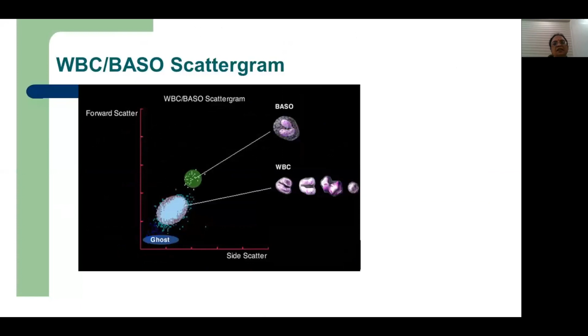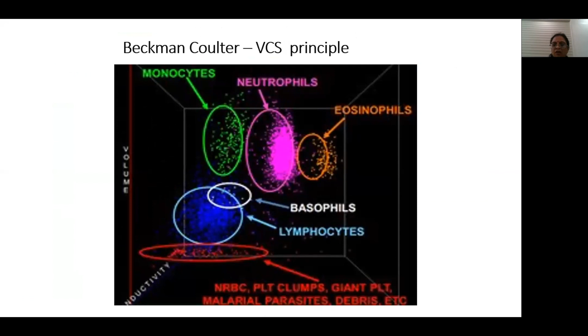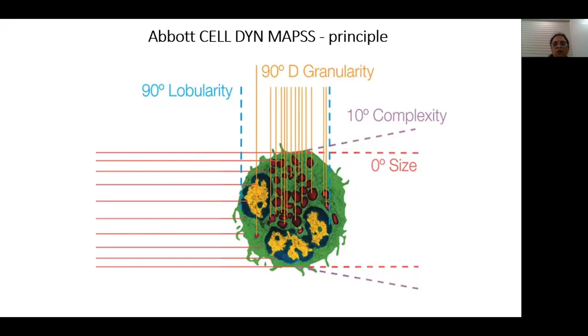And coming to the various hematology analyzers available in the market, Beckman Coulter utilizes the principle of volume, conductivity, and scatter to classify the WBC series. And coming to Abbott, which uses the MAPSS technology, wherein 2 additional light scatters are taken into consideration. The narrow angle light scatter, that is 0 to 10 degree light scatter, is used to note the internal complexity, whereas the 90 degree lateral scatter with depolarization is used to identify eosinophils.